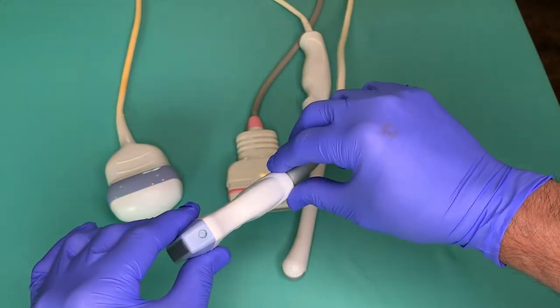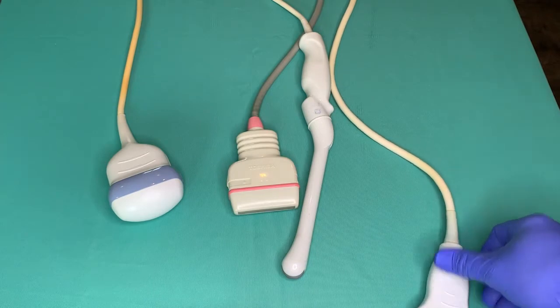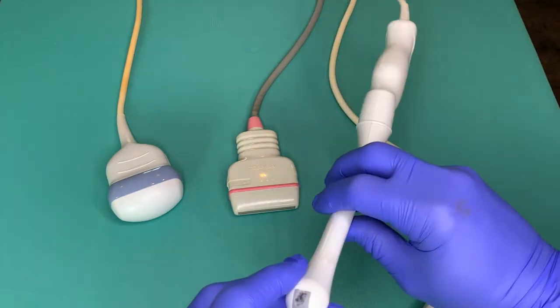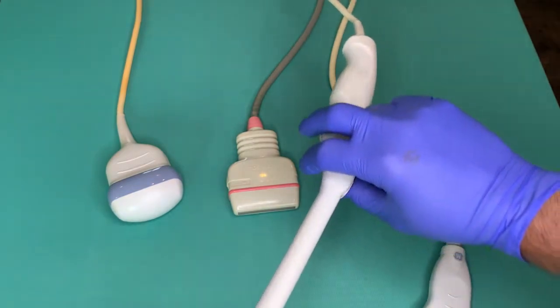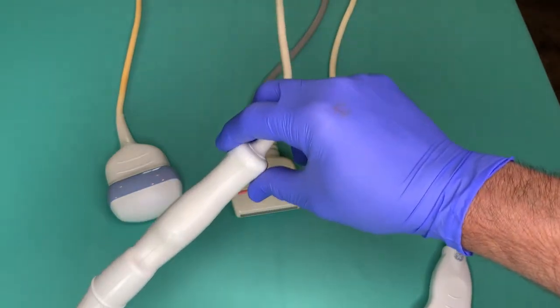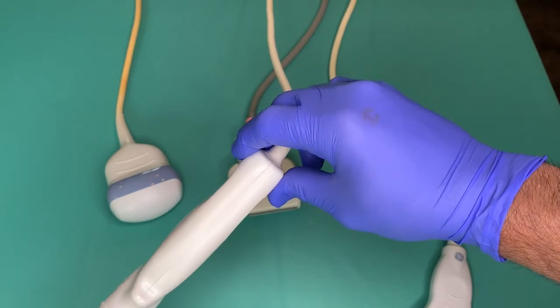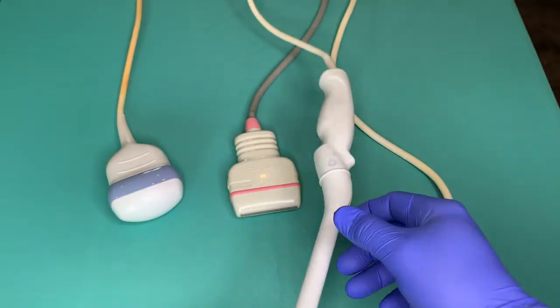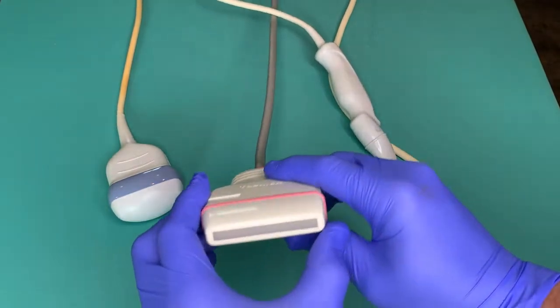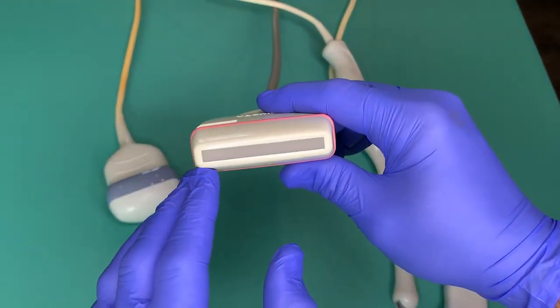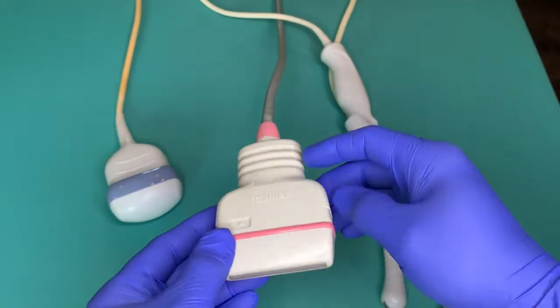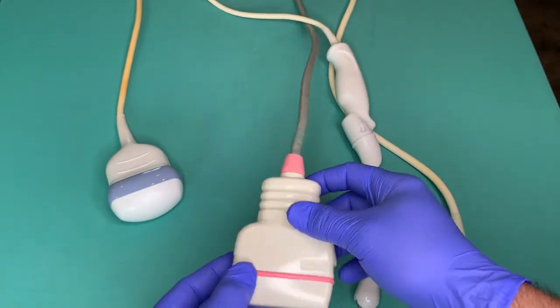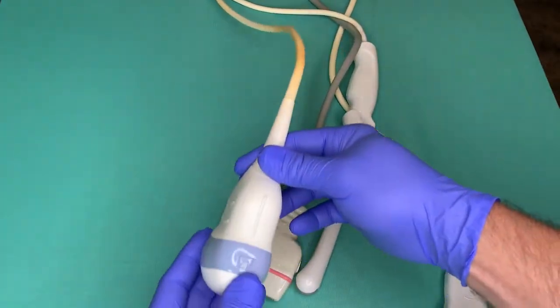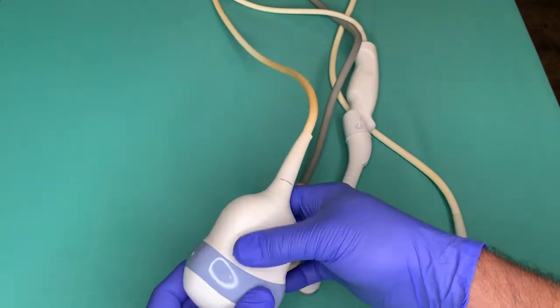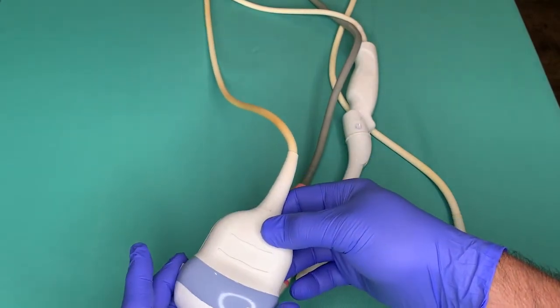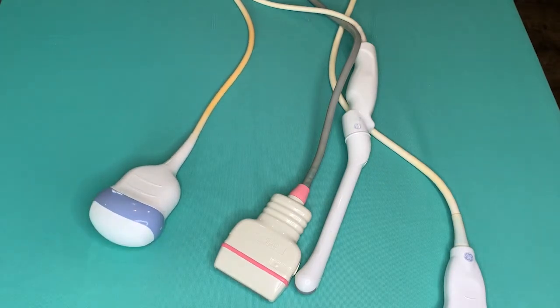The housings are repeatedly exposed to harsh chemical disinfectants multiple times throughout each day. Degradation of materials and adhesives is expected to occur as part of normal wear and tear. Repeated chemical exposure may also cause the housings to become more brittle over time, thus more apt to fracture when exposed to trauma. Tiny openings in adhesive seals and fractures to the housings can permit entry of contaminants such as gels and chemical disinfectants. Inspect the probe housings under magnification, looking for cracks, open seams, or any separations.